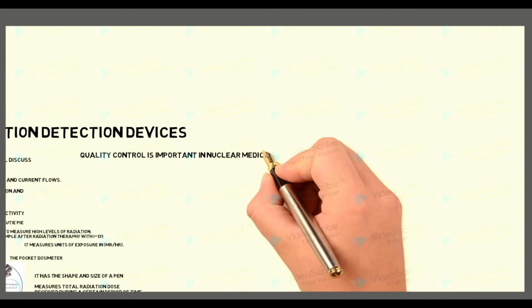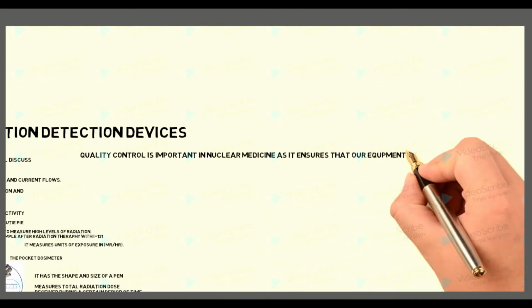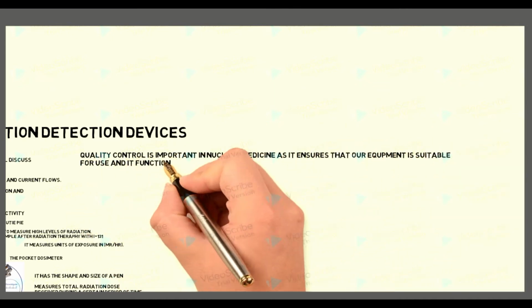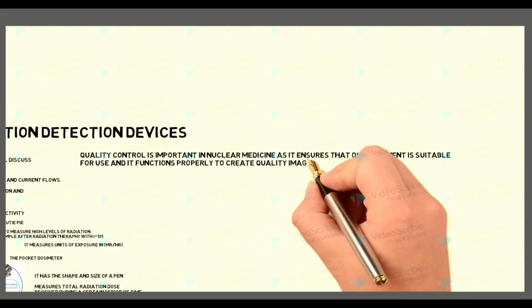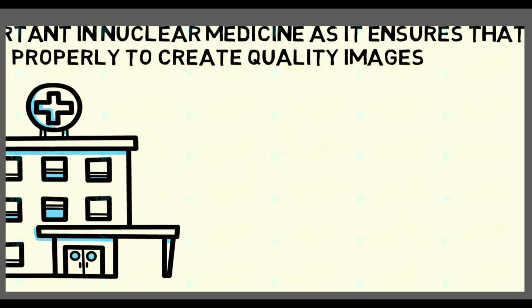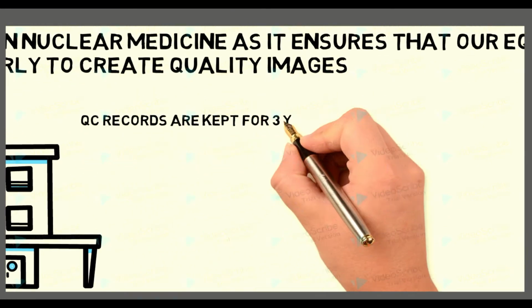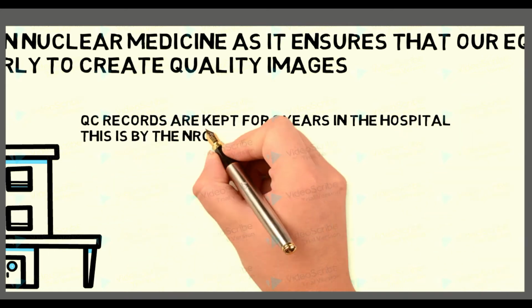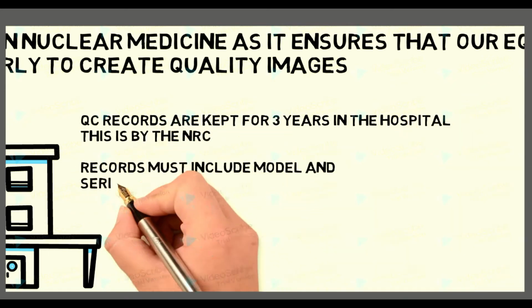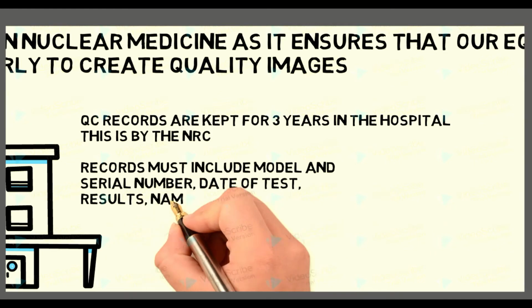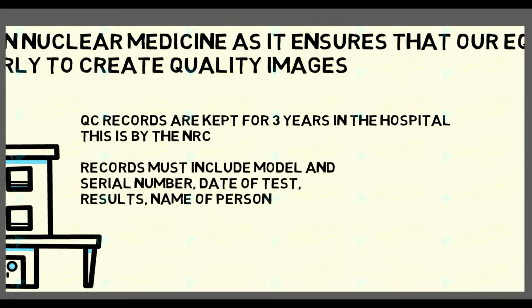Quality control is important in nuclear medicine as it ensures that our equipment is suitable for use and that it functions properly to create quality images. QC records are kept for 3 years in the hospital, and this is required by the NRC. Records must include model, serial number, date of test, results, and the name of the person.